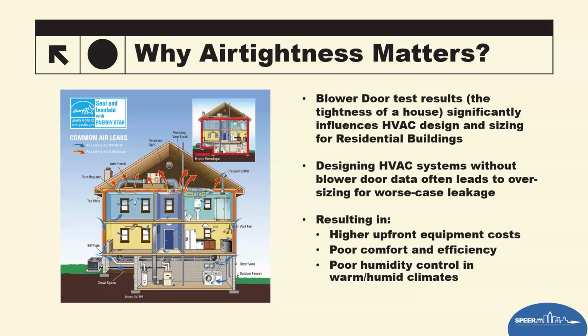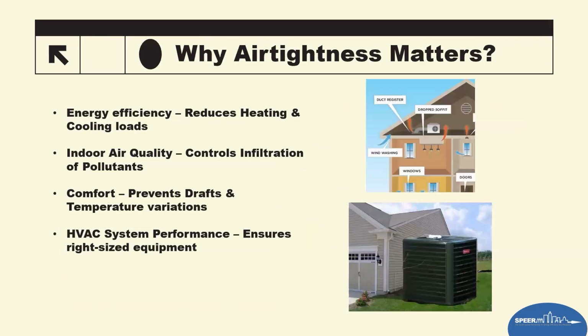Designing the HVAC system without blower door data often leads to oversizing, and worse, by assuming worst-case leakage, it ends up being better than that. Now the system is oversized. This, of course, results in higher upfront equipment costs, poor comfort and efficiency, and poor humidity control in warm and humid climates, which most of Texas is in. As we go through this, you'll see how all of this ties together.